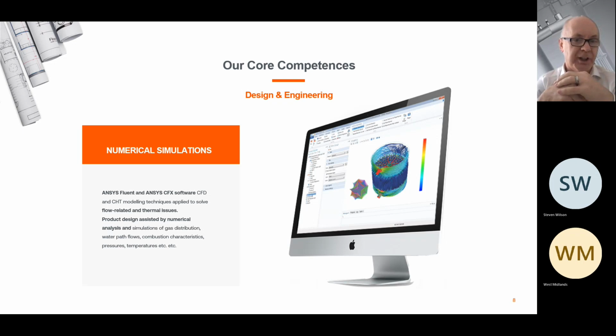Part of our process when we're designing a heat exchanger is we use CFD technology, computational fluid dynamics, through ANSYS software. We design and simulate a heat exchanger using this software so that we can see its efficiency. We can see the flow of the flue gases and the flow of the liquid within the heat exchanger, and we can see where there's a potential problem and change it. By creating turbulence in the flue gases going through the heat exchanger and also in the liquid, we maximise the surface area and the heat transfer, to make it the most efficient heat exchanger that we can.